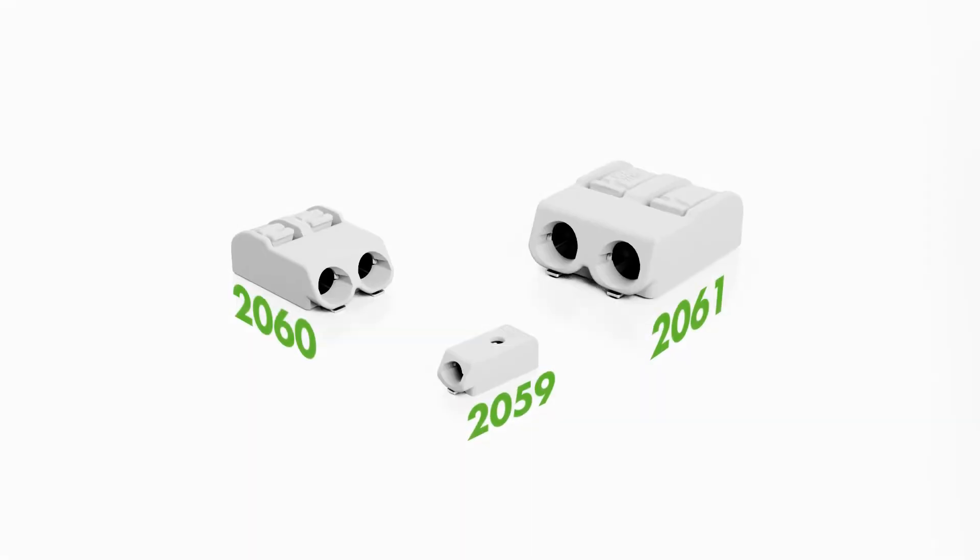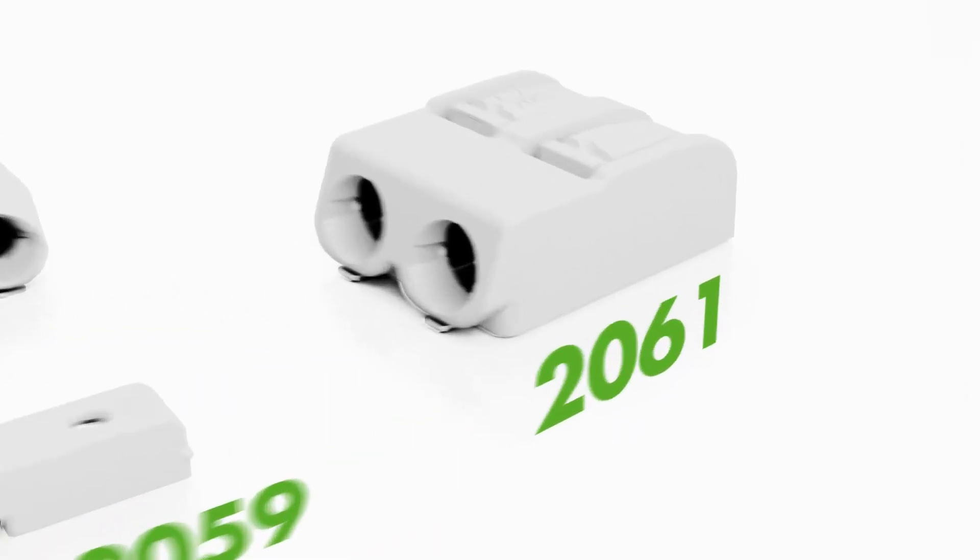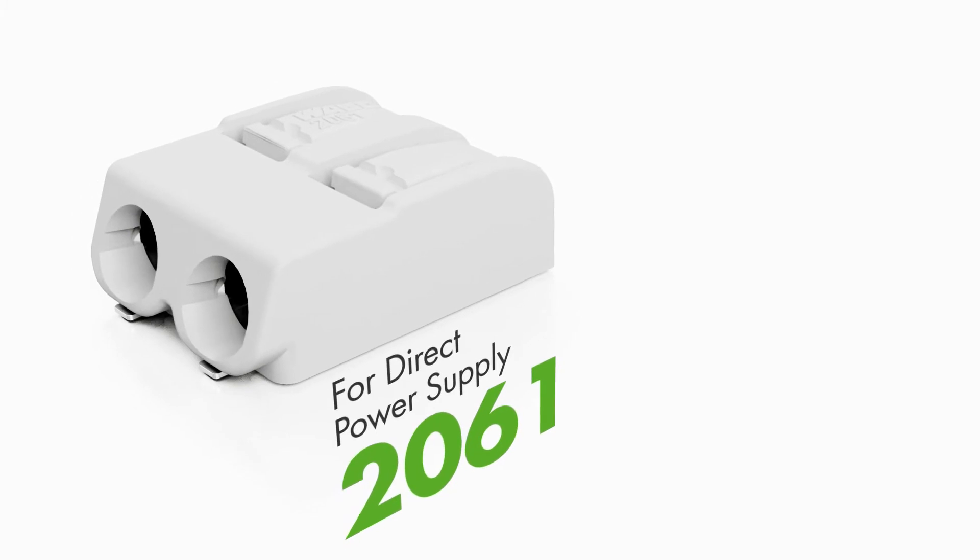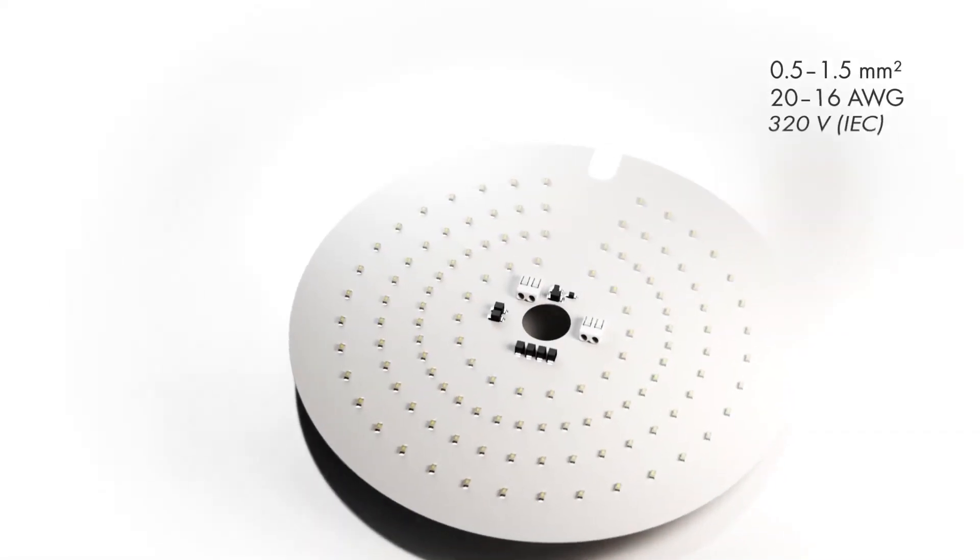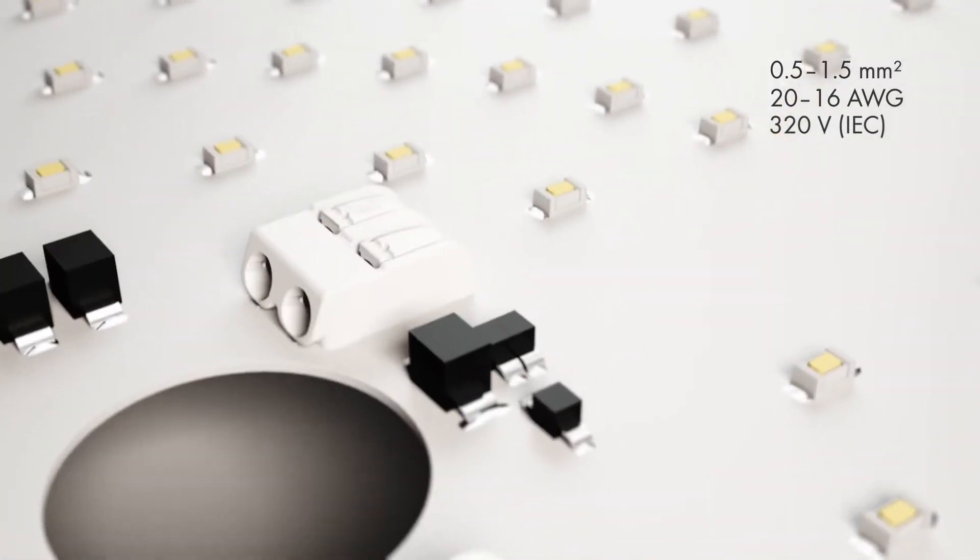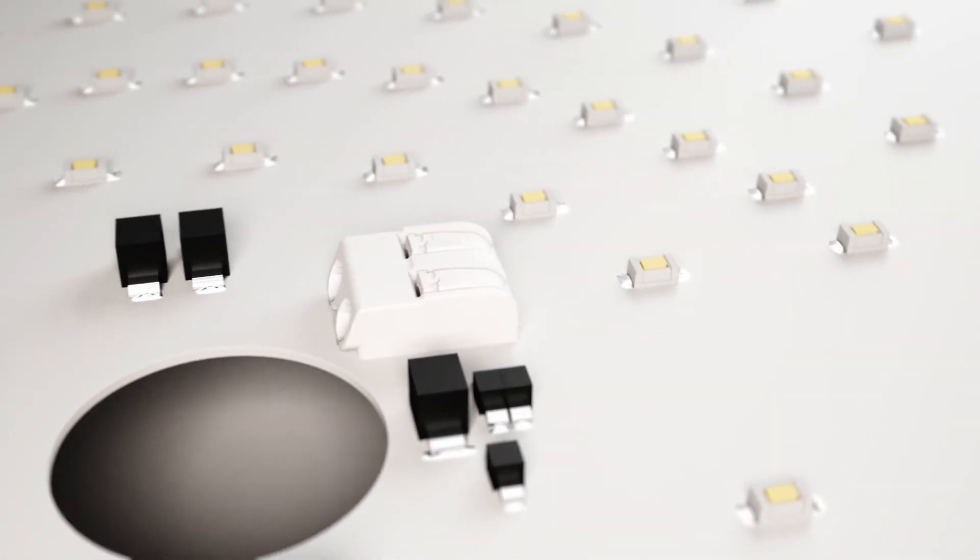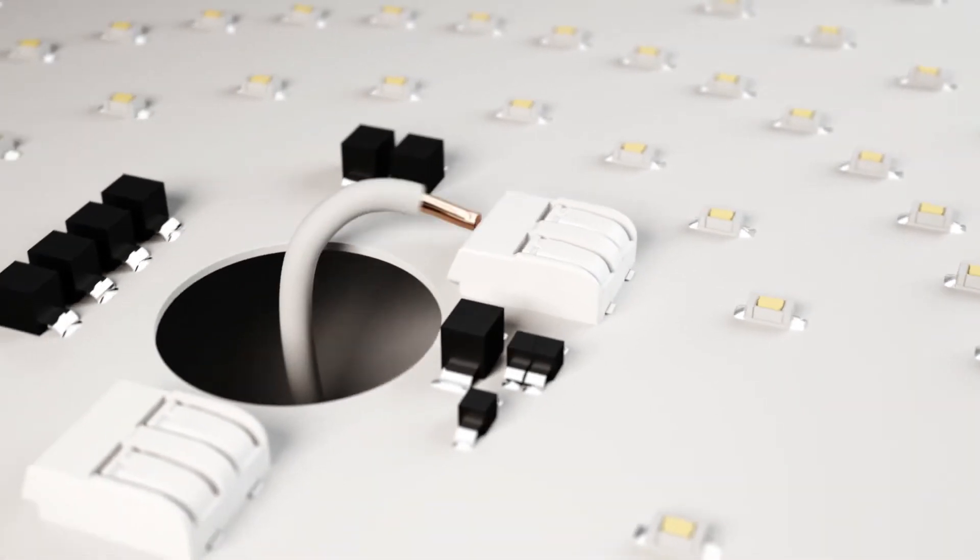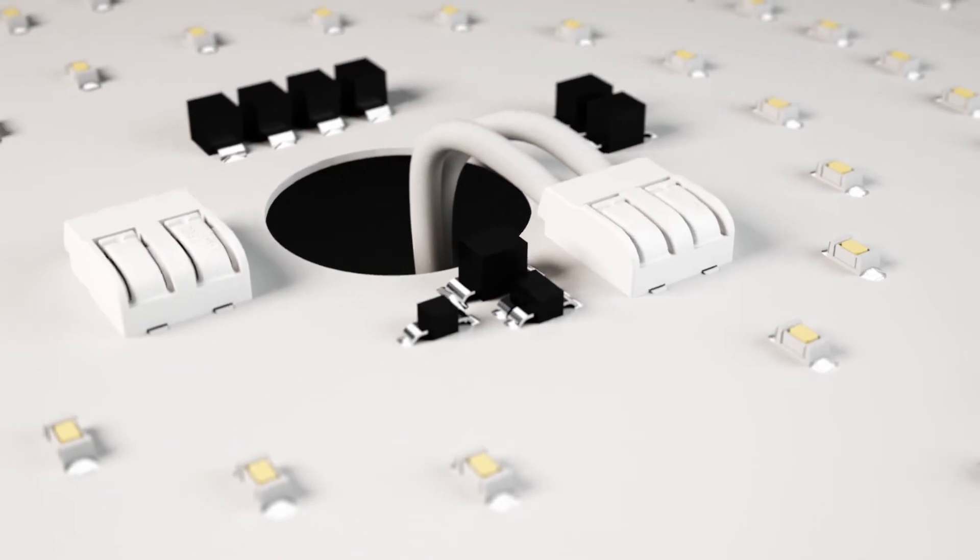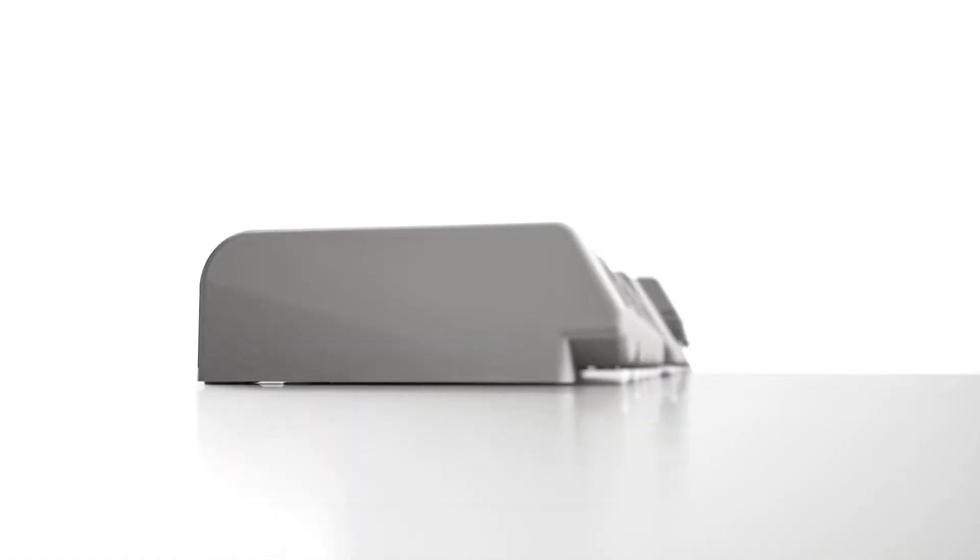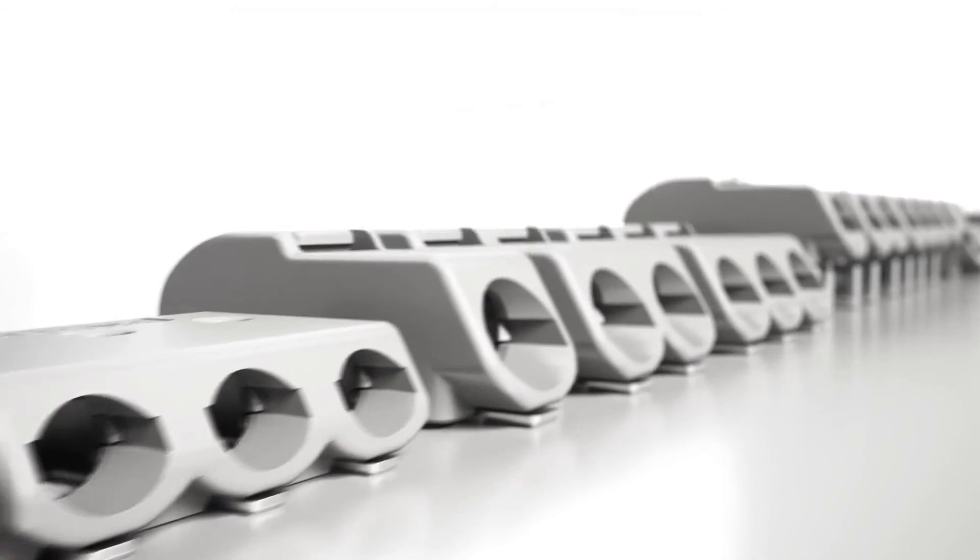2061 series is the ideal solution for directly connecting a power supply to an LED module. These terminal blocks feature an extended nominal cross-section of 16 AWG or 1.5 square millimeters and a nominal voltage of 320 volt IEC and 300 volt UL 1059, making them ideal for industrial applications and direct LED module supply.